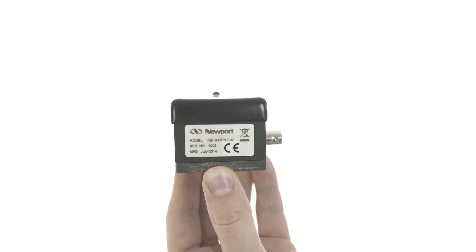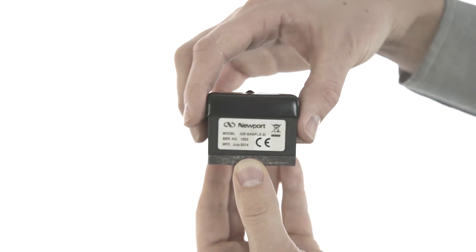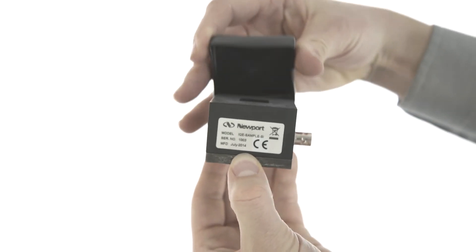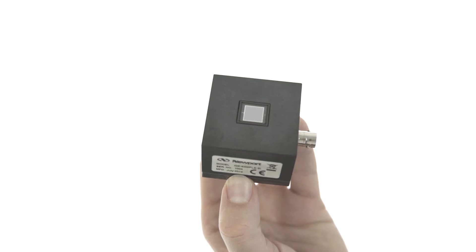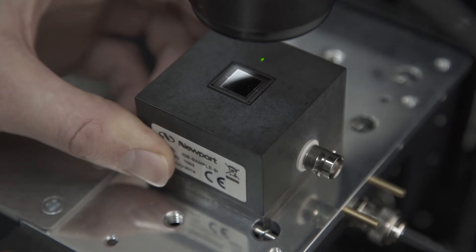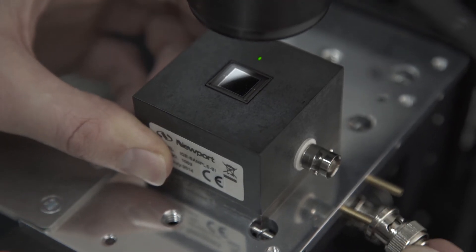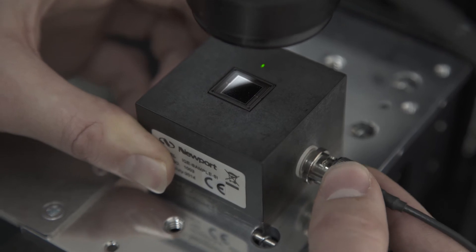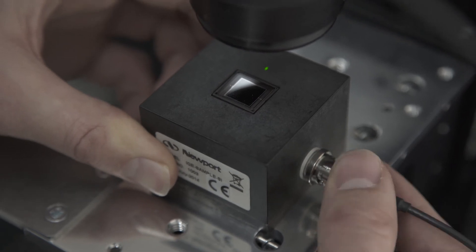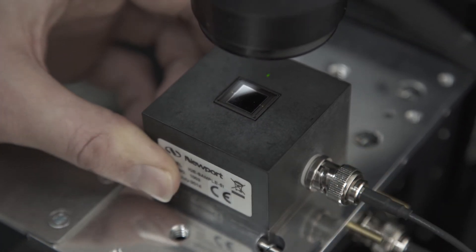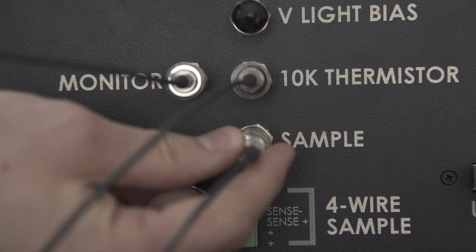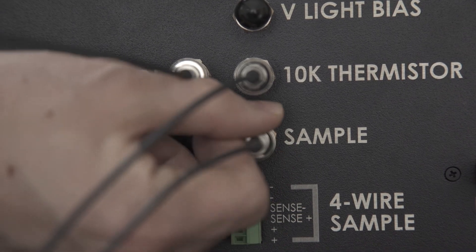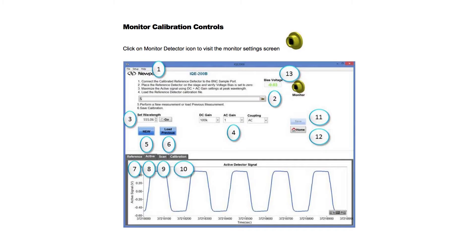This is the reference standard used to calibrate the monitor detector and ensure accurate external quantum efficiency measurements. We make electrical connection using the supplied BNC cable to the port labeled sample on the back of the instrument. Its calibration file has been provided with the system and will be loaded during the calibration process as detailed in the manual.